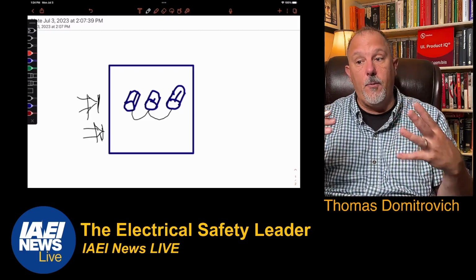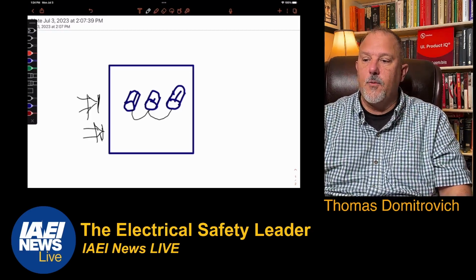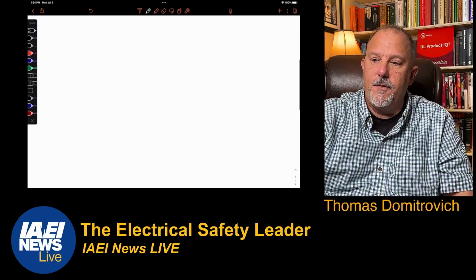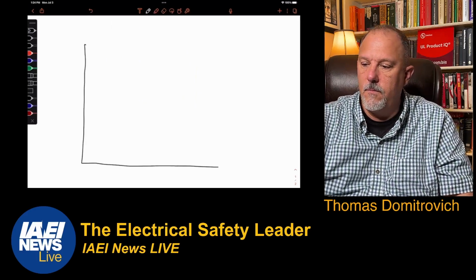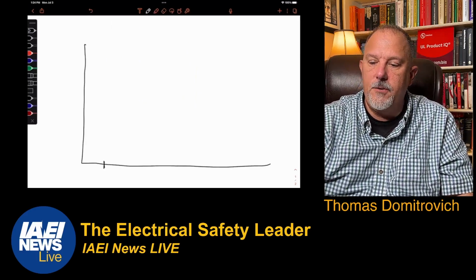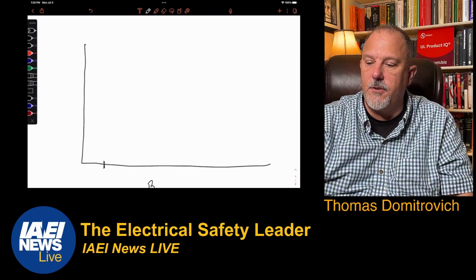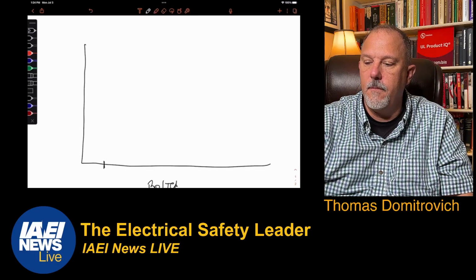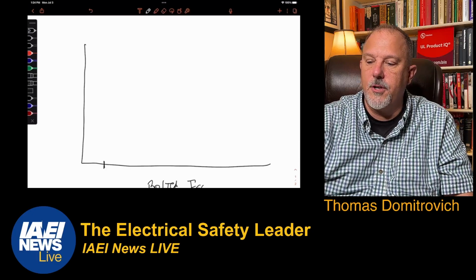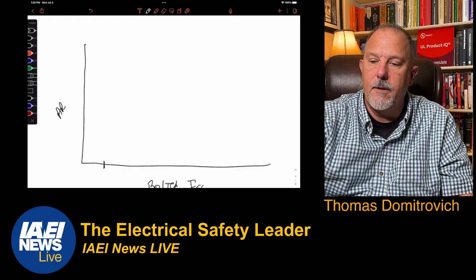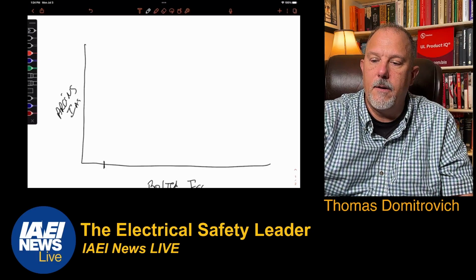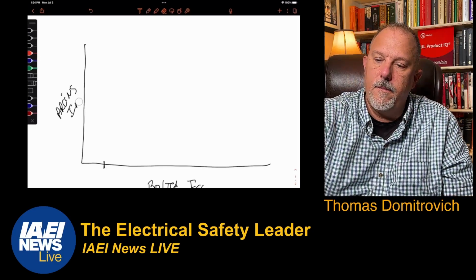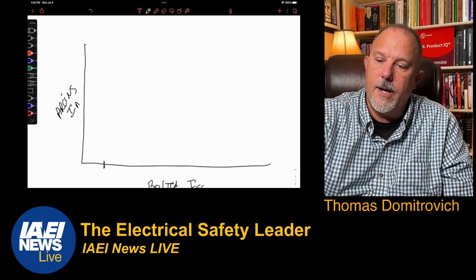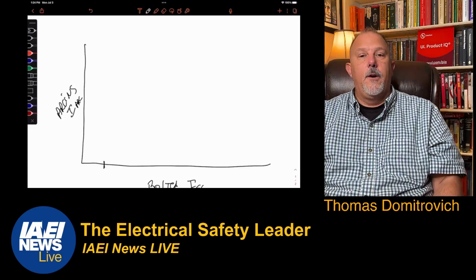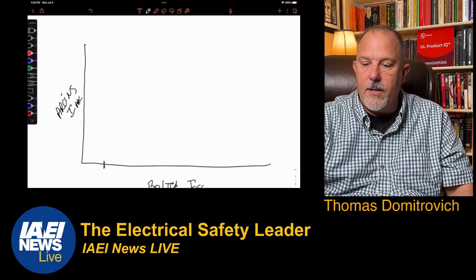And then what we do is we create a curve. Across the bottom is bolted fault current value, bolted I short circuit, and we'll call this I arcing, I arc. All right. So then we say, okay, let's hit it with 10K.